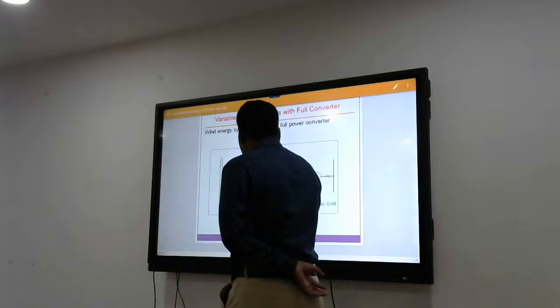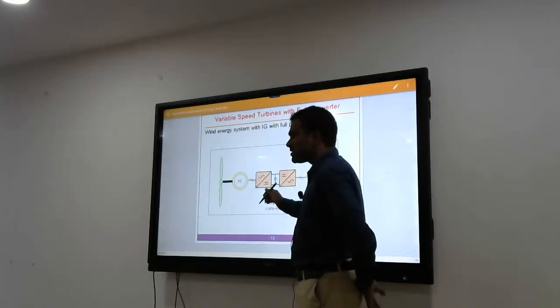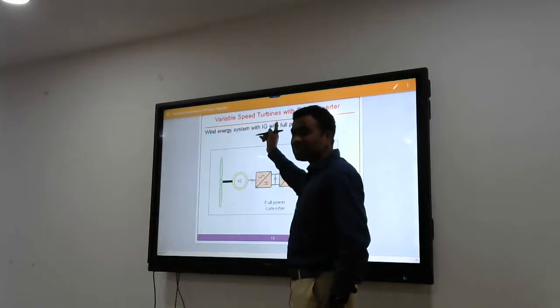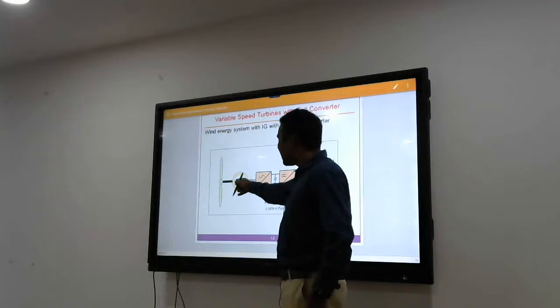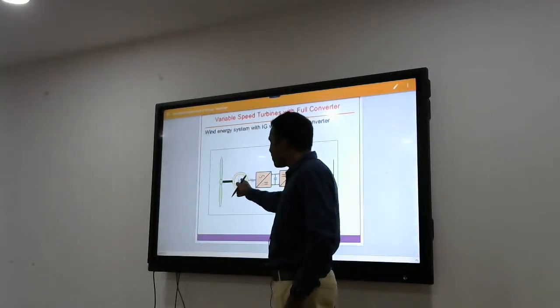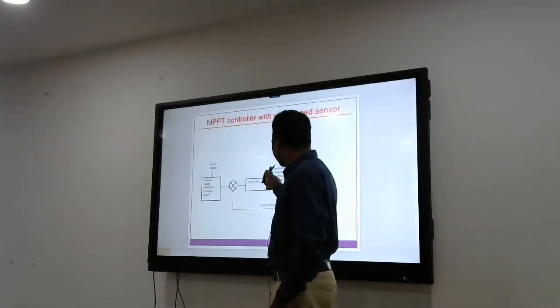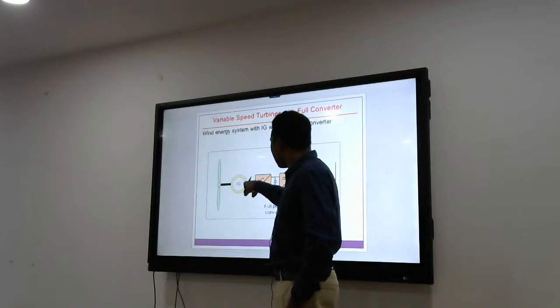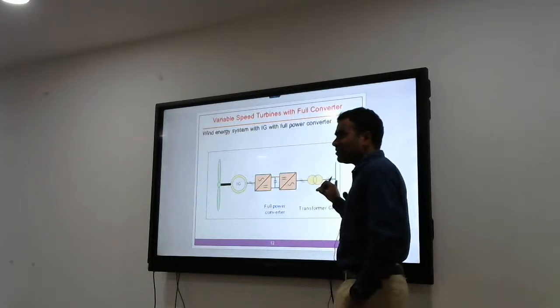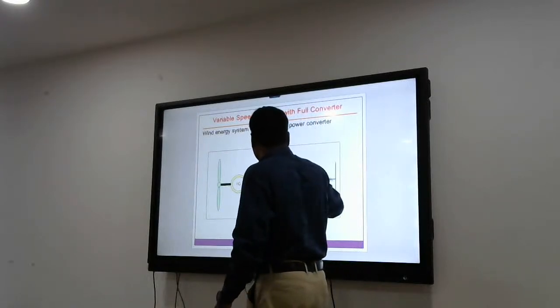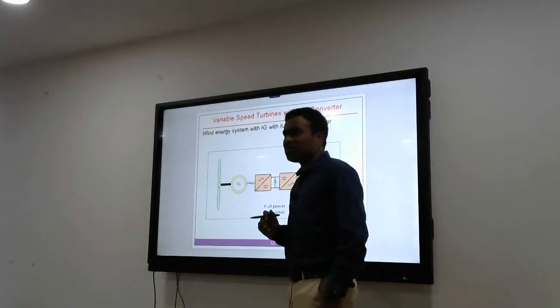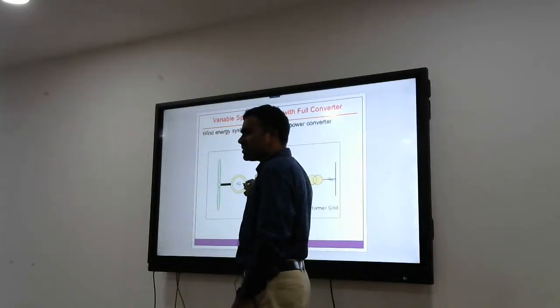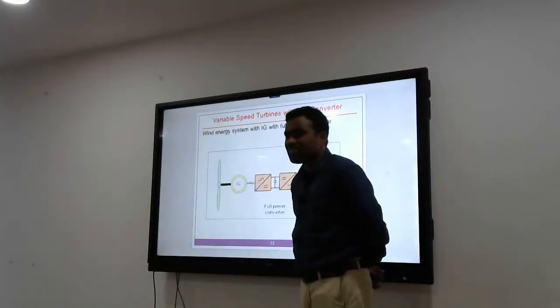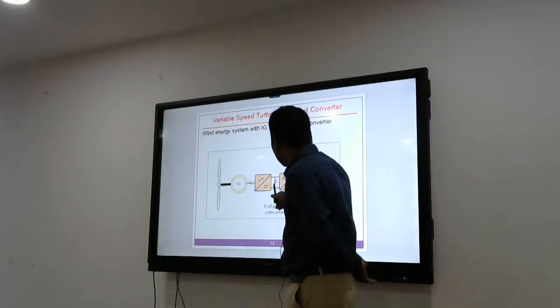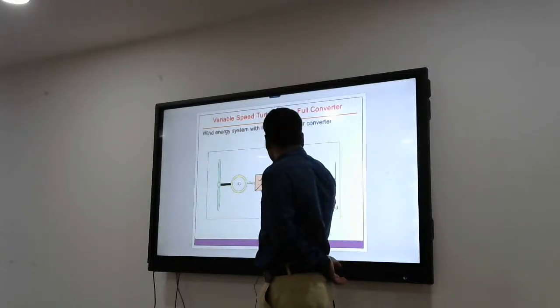Now it comes to the variable speed wind energy conversion system. In this, I mentioned the problem here. This is variable voltage, variable frequency. This is a variable speed wind turbine. As this is a variable speed wind turbine, it is running at variable rotor speeds. If it is running at variable rotor speed, the voltage and frequency that is generated is variable, and the grid frequency and grid voltage is constant. So you have to use this converter scheme to change from variable voltage, variable frequency into fixed voltage, fixed frequency. So you have to convert from this AC to DC and DC to AC.